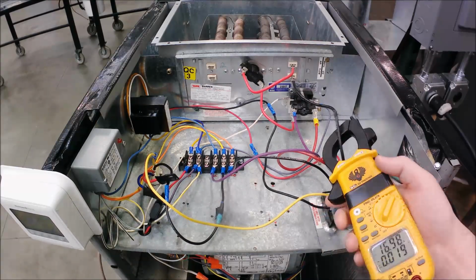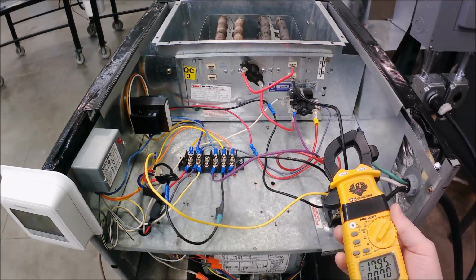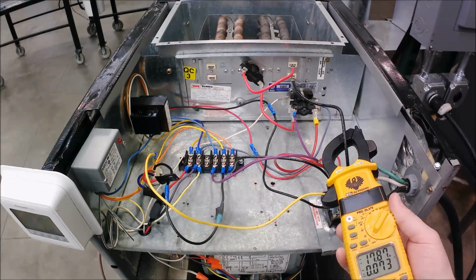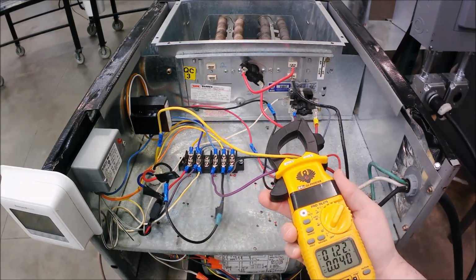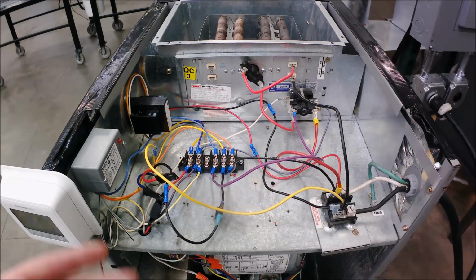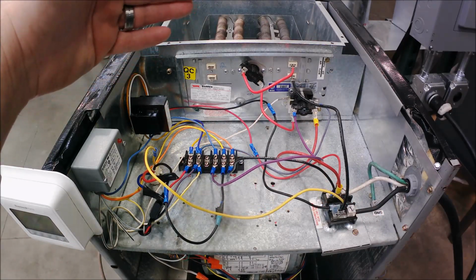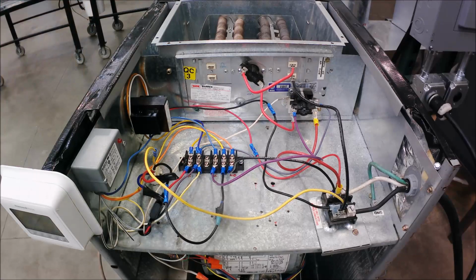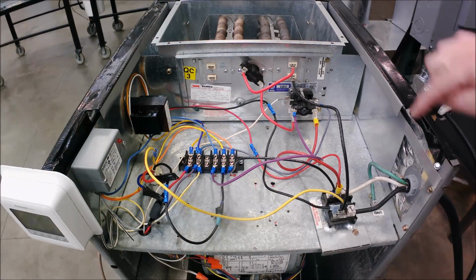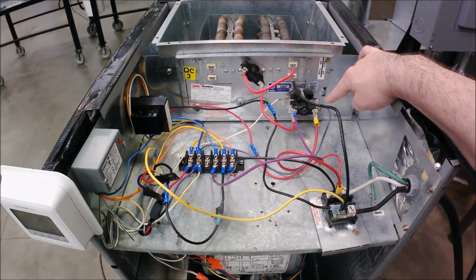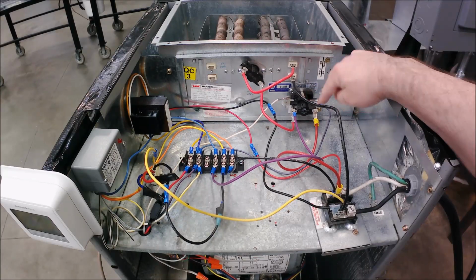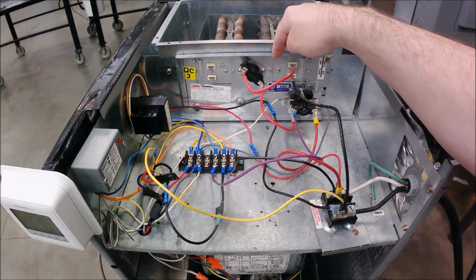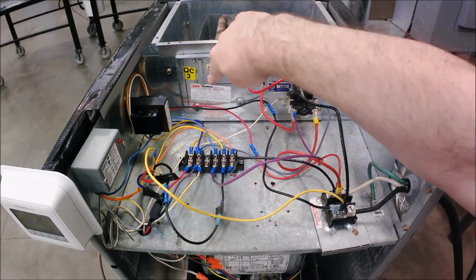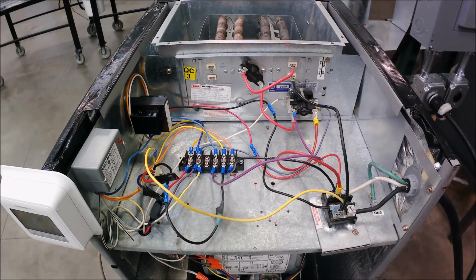Alright, the blower just cut on. I'm pulling 18 amps or so on the heater. Blower's going to pull 1.2. So our heat strips work. Like I said, we could have easily wired in a second heater over here. It would have been the same concept. L1 into the second switch on the sequencer, out of the second switch into the limit, over to the heater, and then back to L2. So same concept, it just repeats.